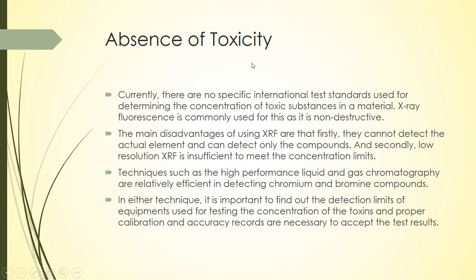So it probably cannot detect the weight percentage of lead. It would say the weight percentage of lead oxide, right? However, the oxide molecule can be more than 0.1%, but lead has to be less than 0.1%. So if you get the actual figure of lead oxide, you do not know exactly how much weight percentage of that lead oxide is actually lead. That detail is not available in X-ray fluorescence.